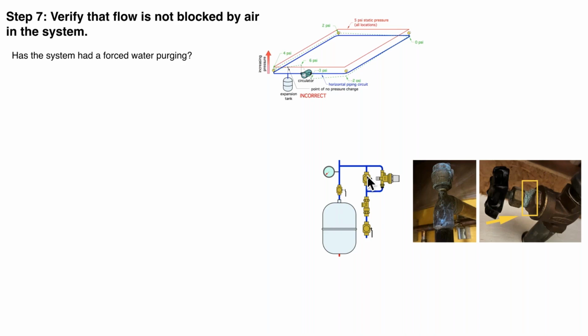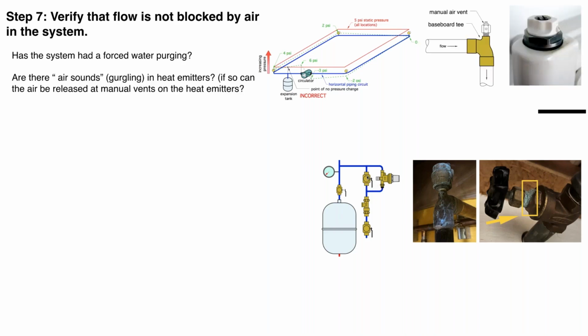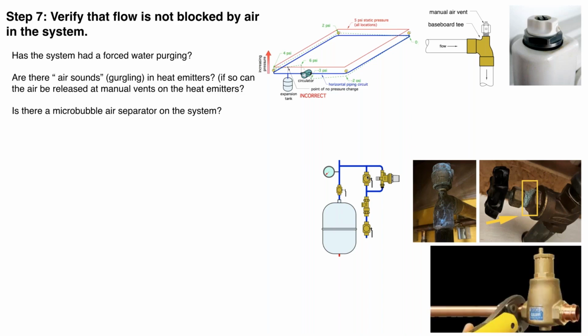Maybe they've just opened a valve and assumed that all the air will rise up regardless of whether the piping goes up, down, and so forth. You could have air trapped in the system that way. So forced water purging is a good way to push as much of that bulk air out as possible. Do you hear gurgling in the heat emitters? It's not uncommon at startup, but a good air separator will take care of that over time. Is there a good microbubble air separator in the system? These do a much better job than the old cast iron air scoops do. They will capture that residual dissolved air over a period of a few days and eject it from the system.